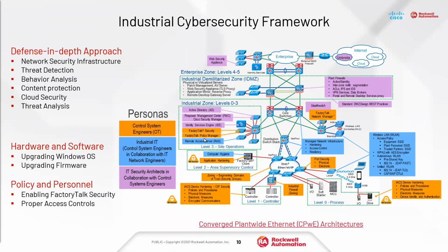On the newer systems, specifically when we start talking about ControlLogix on the L8 platform, the process controllers, the new Ethernet adapter like the EN4TR, this is when we can start looking at leveraging something like CIP security. That provides you the ability of encrypting at the protocol level, making a secure connection between your controllers and the SCADA DCS environment.